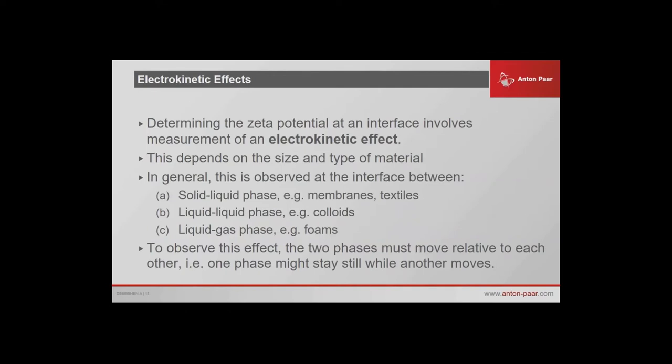An electrokinetic effect is what we use to measure a Zeta potential — it is something mechanical which causes shear of the charge, or something electrical that causes mechanical movement. You must do one or the other to have an electrokinetic effect. It depends on the size and type of material. If you have giant rocks, you can't move them, so you measure around them. If you've got colloidal systems, you can stream them across by applying a charge and they would move. The phases must move relative to each other — one could stay still while the other moves, or they can both move in opposite directions, but you must have movement to measure an electrokinetic effect.